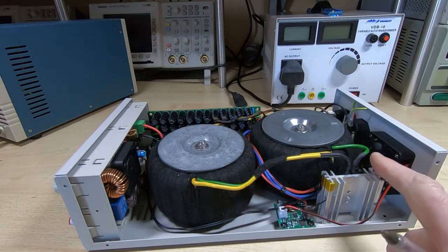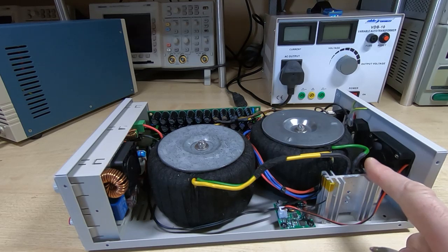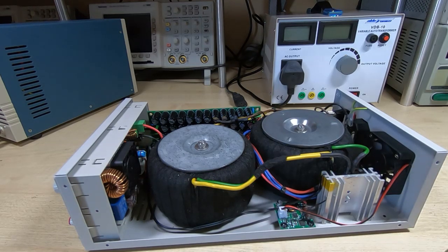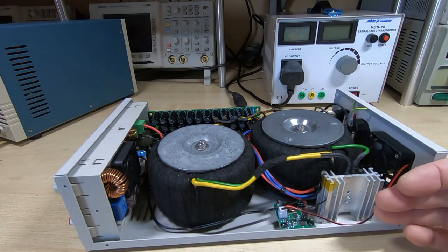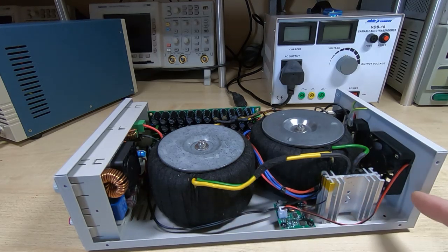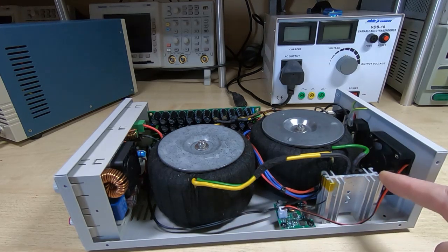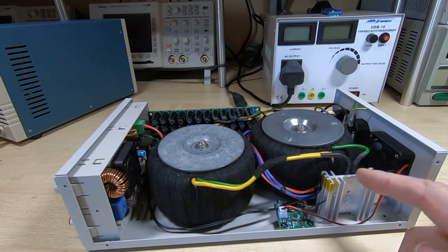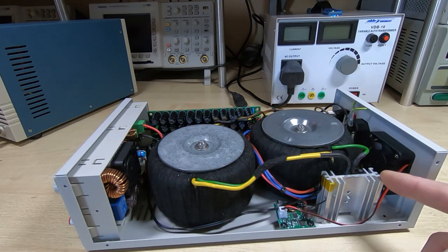This thing runs quite cold. As you saw, it gets up to around 40 degrees with the cover off, but with the cover on, air is being drawn down through here and past both sides of the heatsink, so this temperature drops a lot once the cover's on, and it sits at full load. It sits at about 35-36 centigrade, and that's obviously very reasonable. These rectifiers are rated up to over 100 degrees C.